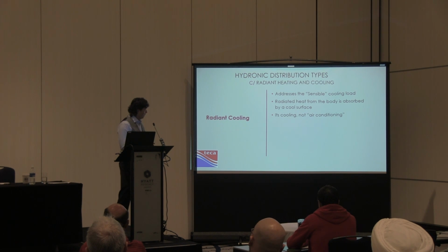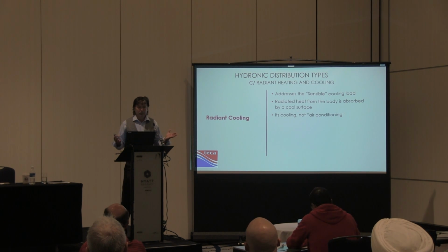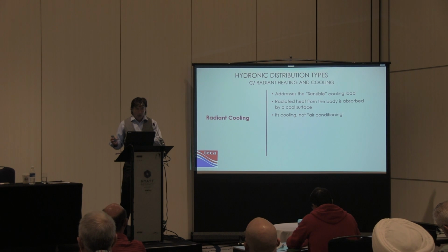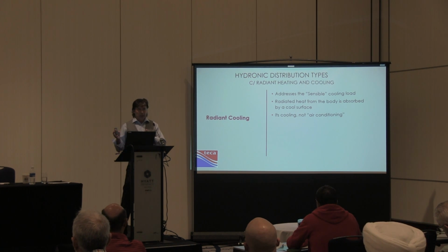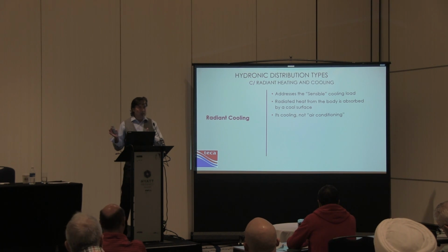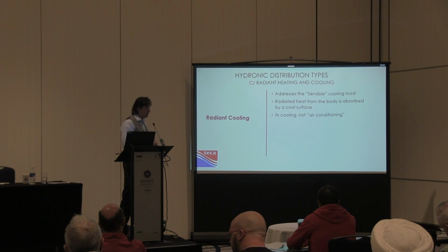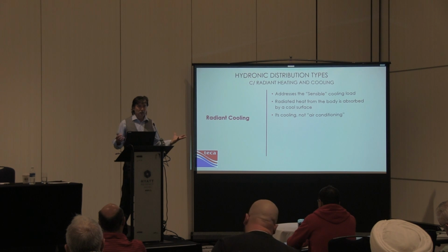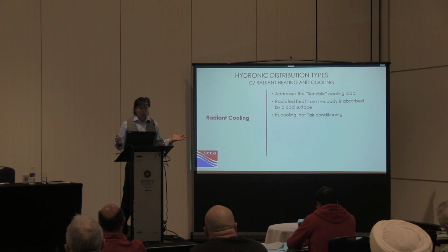When we talk about the sensible load, in the air we have a sensible heat and we have a latent heat. Sensible heat is the heat that you can sense. Latent heat is the actual moisture in the air. And for the most part, that's the uncomfortable bit. Our sensible load here is 70 on average, depending on the time of year, of course. And then you've got your latent load, which is your moisture load. With radiant cooling, where you're just accepting radiated heat, you're only dealing with the sensible heat component. Latent heat, the moisture, how can we remove moisture with a radiator? It just doesn't happen. In fact, you've got to go through extra lengths so it doesn't happen.